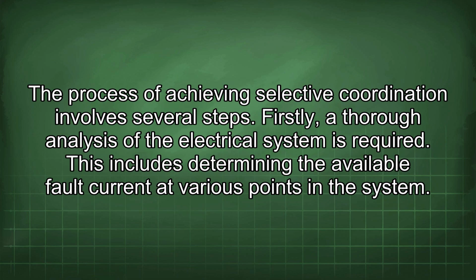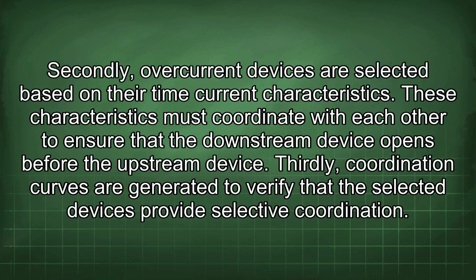The process of achieving selective coordination involves several steps. Firstly, a thorough analysis of the electrical system is required. This includes determining the available fault current at various points in the system. Secondly, overcurrent devices are selected based on their time current characteristics. These characteristics must coordinate with each other to ensure that the downstream device opens before the upstream device.